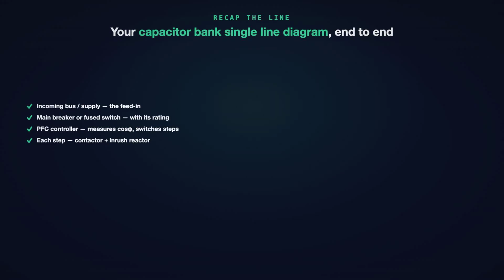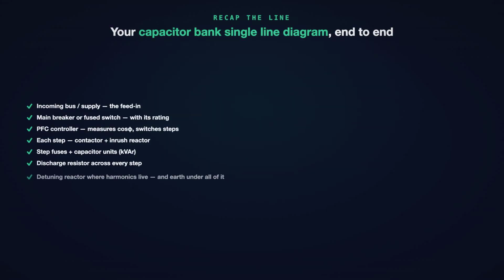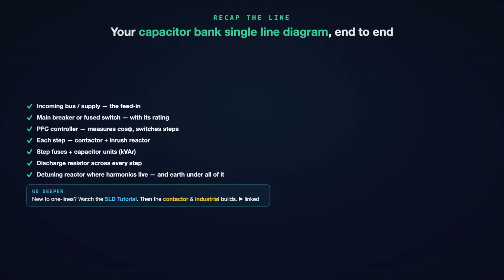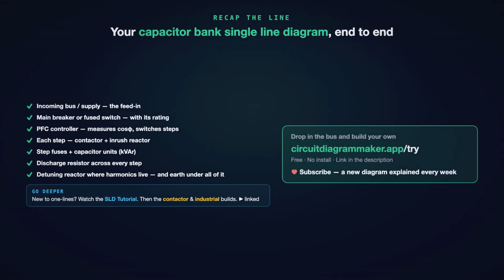Let's recap the line. The incoming bus and supply. A main breaker or fuse switch with its rating. The PFC controller measuring power factor and switching the steps. Then each step, a contactor, an inrush reactor, the step fuses, and the capacitor units. A discharge resistor across every step. A detuning reactor in series where harmonics live. And earth bonding all of it together.